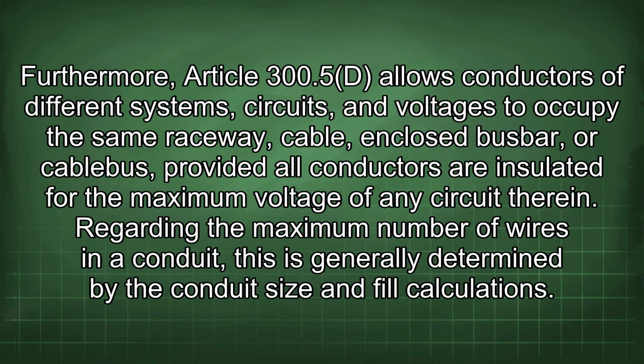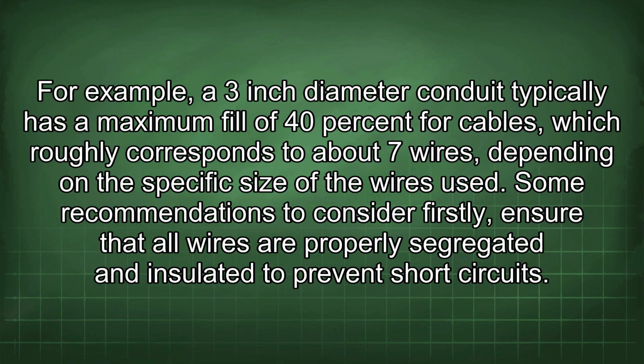Furthermore, Article 300.5d allows conductors of different systems, circuits, and voltages to occupy the same raceway, cable, enclosed busbar, or cable bus, provided all conductors are insulated for the maximum voltage of any circuit therein. Regarding the maximum number of wires in a conduit, this is generally determined by the conduit size and fill calculations. For example, a 3-inch diameter conduit typically has a maximum fill of 40% for cables, which roughly corresponds to about 7 wires, depending on the specific size of the wires used.